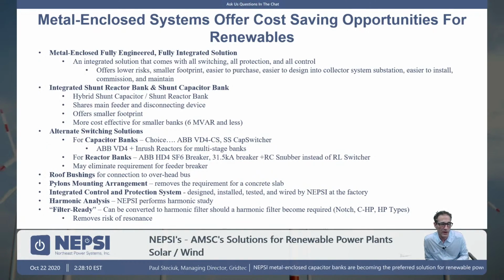NEPSI can be involved with the harmonic analysis. We could tell you what the possibility of resonance is, if you should be buying harmonic filters, and we can oftentimes do this at a very competitive price, and oftentimes we will include it with the metal enclosed cap bank if you purchase from us. And then we always, of course, recommend filter-ready cap banks because harmonic studies are often very inconclusive. So we recommend that you buy a filter-ready cap bank and do a wait-and-see mentality.